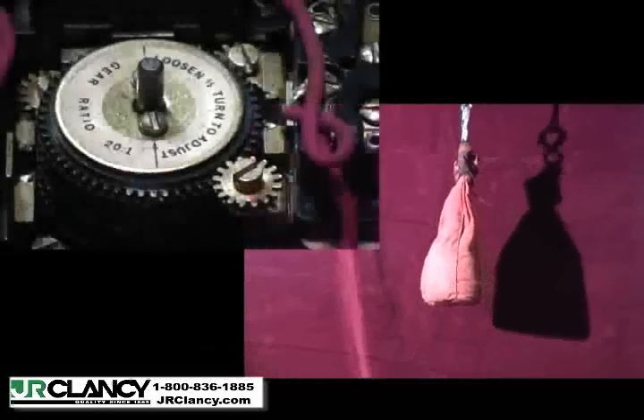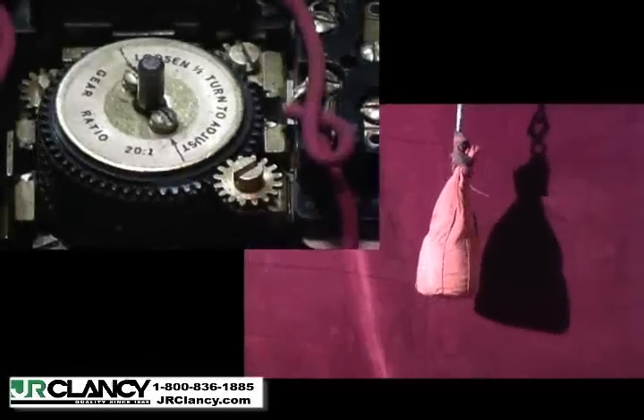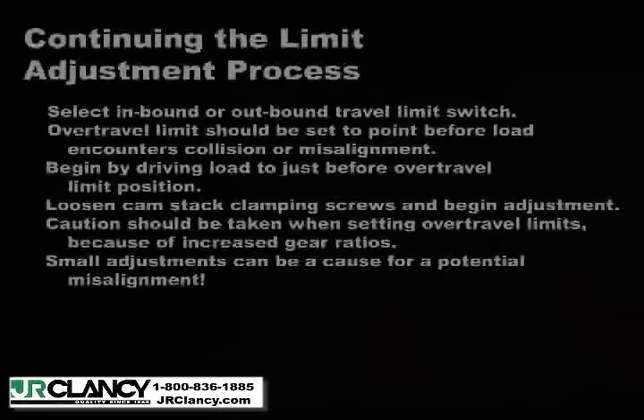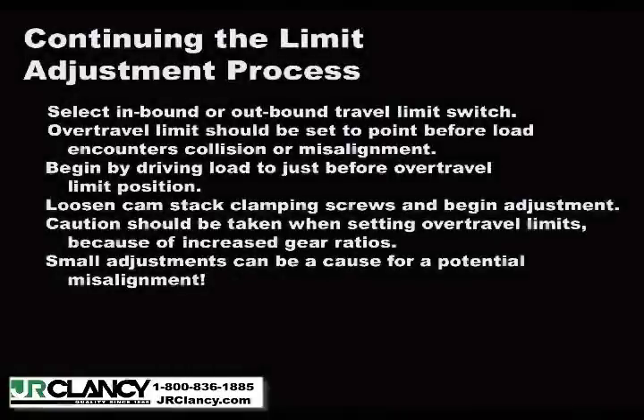We can see the cam stack rotating as our load travels, or jogs, towards its inbound spike. We have selected to set our inbound limits first. The over travel limit should be set to the point before the load encounters collision or misalignment. Begin by driving the load to just before the over travel limit position, then loosen the cam stack clamping screws and begin adjustment.